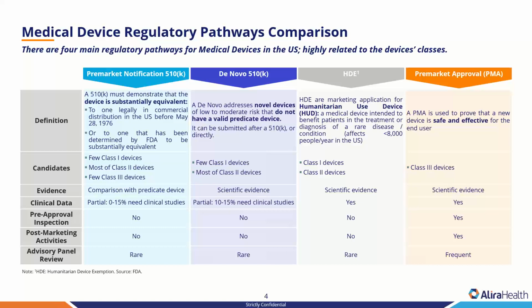The next on the screen in gray is the humanitarian device exemption submission. It's a submission to the FDA for a product intended to diagnose or treat a rare disease that affects less than 8,000 people per year in the United States. Class 1 and Class 2 devices can fall under this humanitarian device exemption status, and a good amount of scientific evidence as well as clinical trial data are required to get an HDE approved. And then lastly, on the very right side, is the PMA process, pre-market approval. It's for the highest risk devices, Class 3 devices. An extensive level of scientific evidence is required, including clinical trials, preclinical, and animal studies.